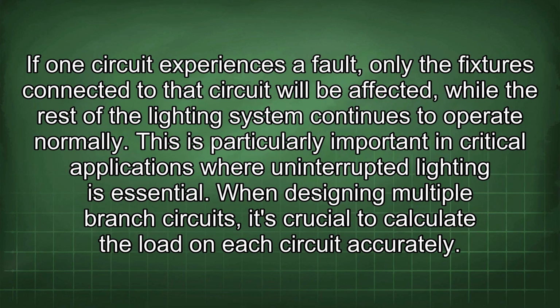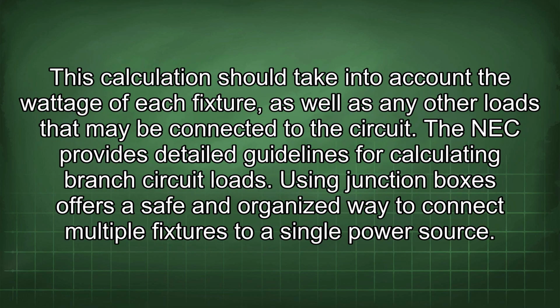If one circuit experiences a fault, only the fixtures connected to that circuit will be affected, while the rest of the lighting system continues to operate normally. This is particularly important in critical applications where uninterrupted lighting is essential. When designing multiple branch circuits, it's crucial to calculate the load on each circuit accurately. This calculation should take into account the wattage of each fixture, as well as any other loads that may be connected to the circuit. The NEC provides detailed guidelines for calculating branch circuit loads.